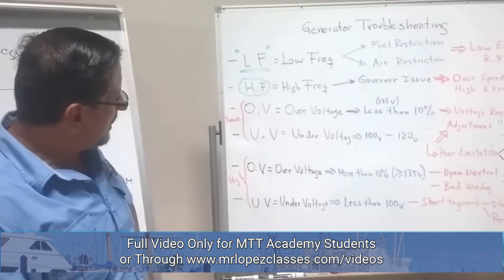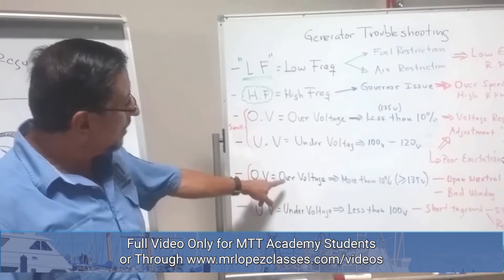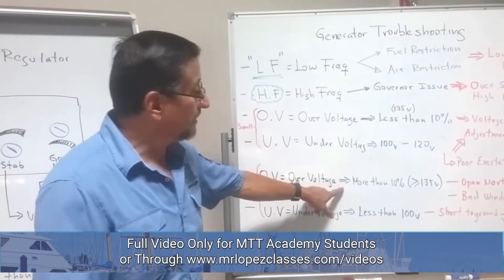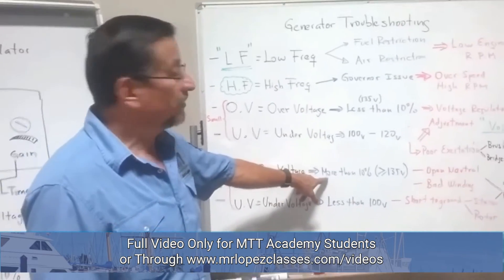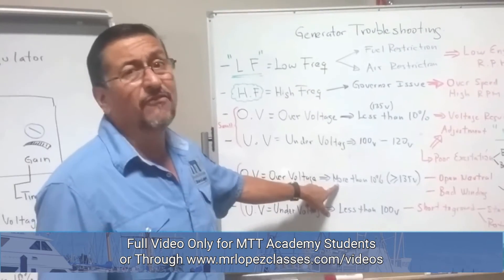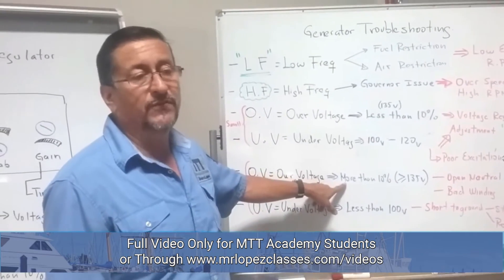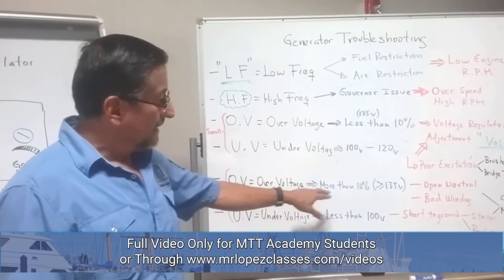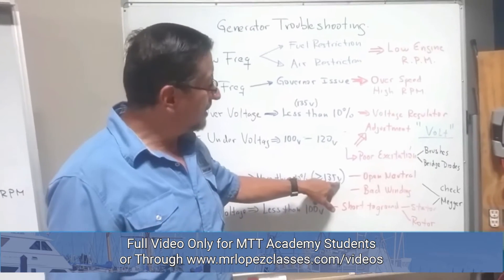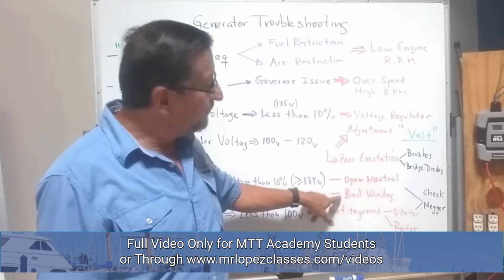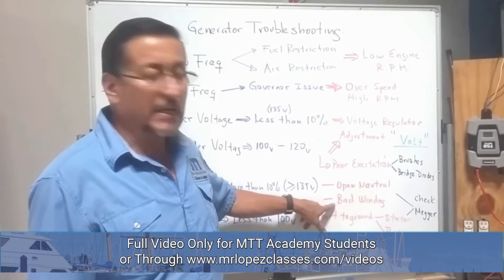If the output voltage is high — over voltage, more than 10% — for example, the output voltage is 150 or 160 volts instead of 120, you have two possibilities. One possibility is an open neutral. The other possibility is a bad winding.